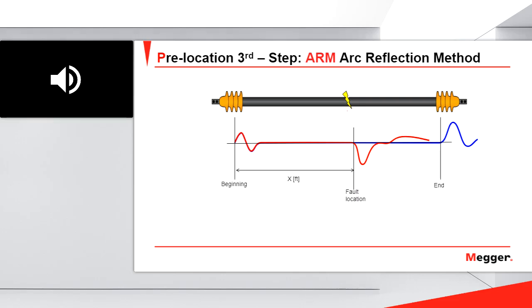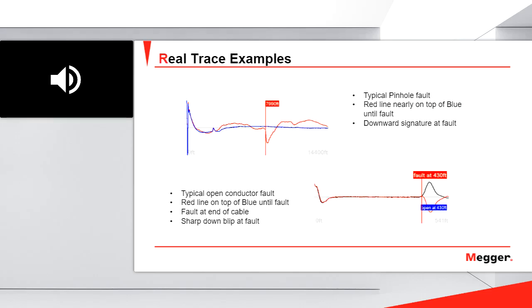Before that, let me show you some real traces. You can see, for instance, in the first trace in the upper left, that even when we have a lot of noise, the point where we have the fault is very clear to see. You can see very clearly here the downward reflection and the downward blip. And in the case where we have a fault at the end of the cable, you can see very clearly the separation of the low voltage trace and the high voltage trace. So, some real traces that I wanted to show you.